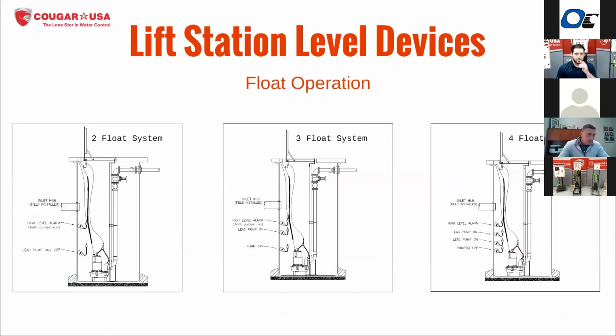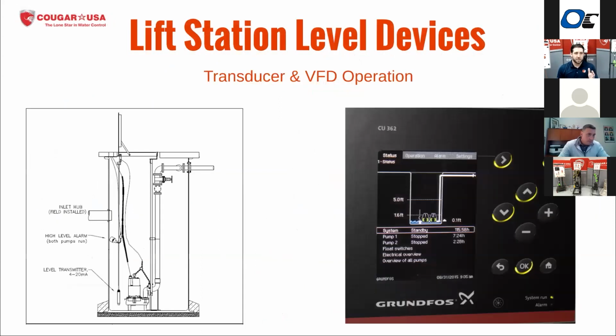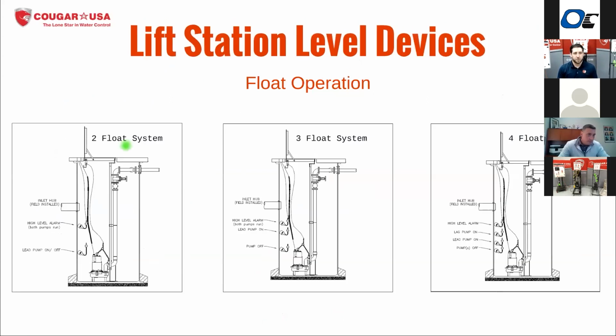Okay. Float operation, again, going to demonstrate these on the control panel, but I do want to cover the basic designs here. So on the left-hand side, the two float system can be used for a single pump application. So simplex operation, where your bottom float switch is turning the pump on and off, and you get your high level here on the second one. And it can also be used as a simple way to control two pumps, in that this bottom float switch is turning this pump on and off. And the second float switch there is both a high level alarm as well as turning on the lag pump.